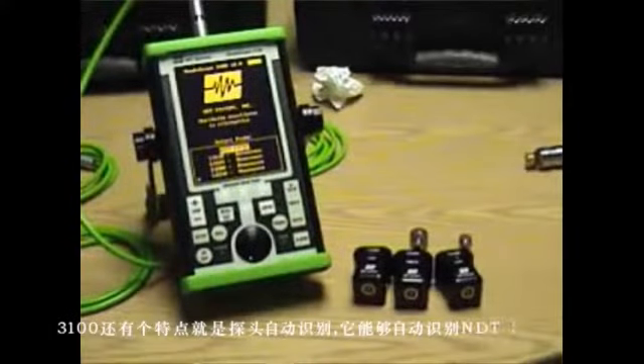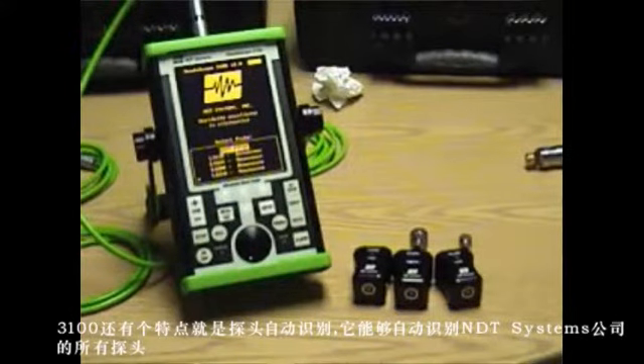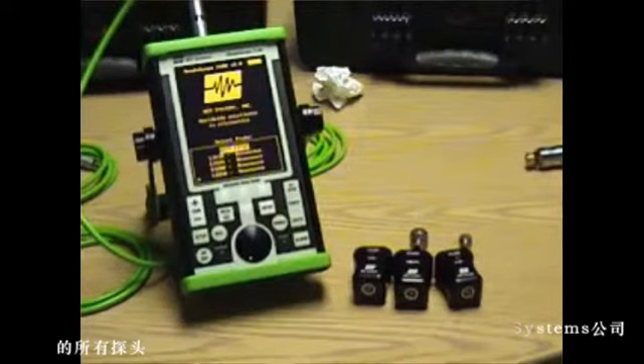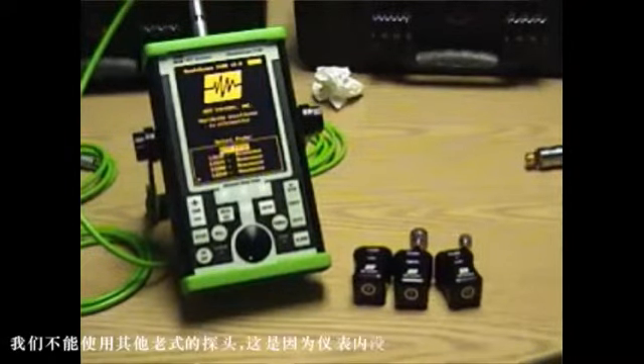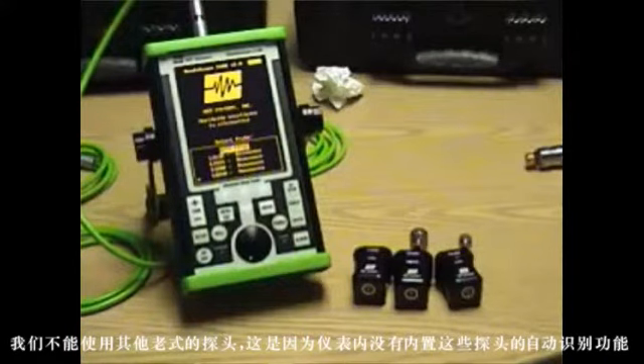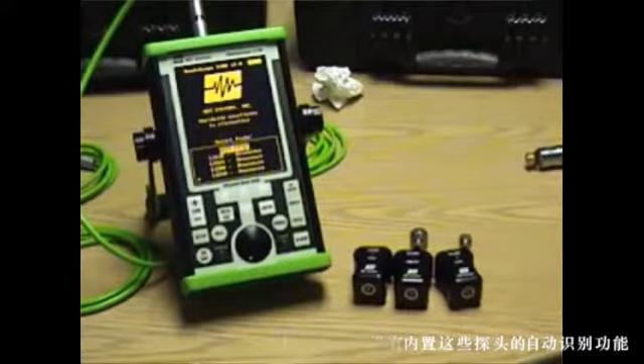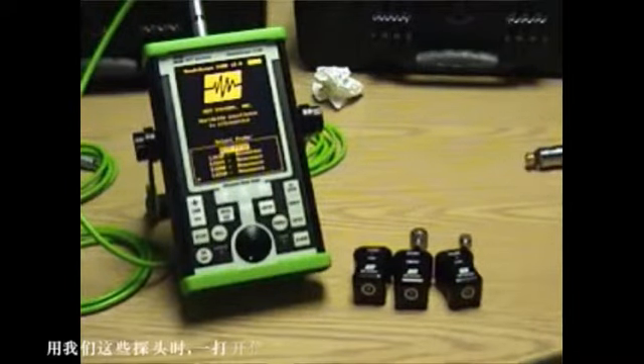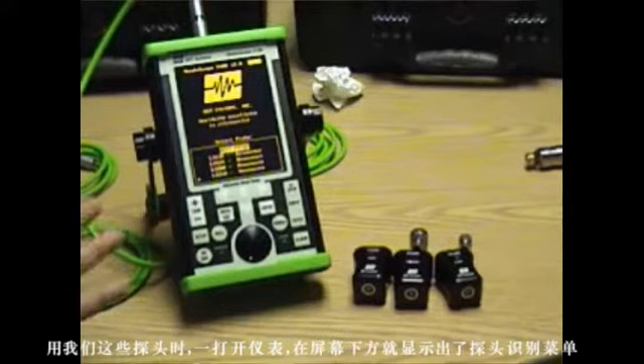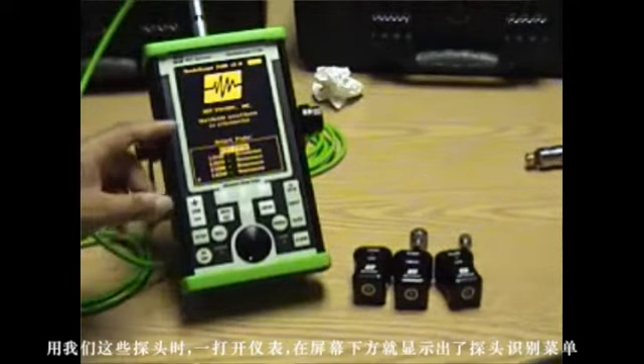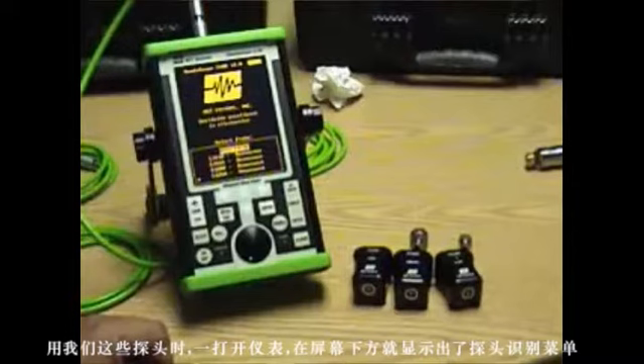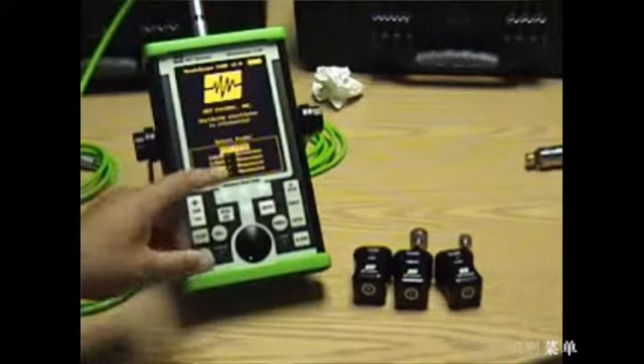One of the features of the 3100 is automatic probe recognition. It will recognize all of the probes that are built for the unit by NDT systems. We can use other Stavely type probes, but they do not have the probe recognition characteristics in them. We have to do another step. But for our probes, when you turn the gauge on, you'll have a select probe menu that appears on the bottom of the screen.